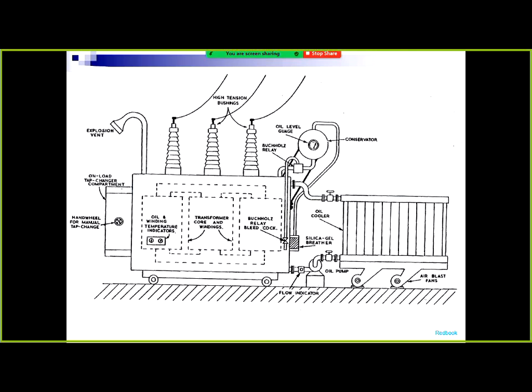So this is a typical looking transformer. It's a bit of an old picture. We don't have a hand wheel for the manual tap changer on the bottom left corner anymore. You've got the windings inside there. On the right hand side you've got your cooler, and that can be just natural convection, or it could be with pumps pumping it around, or pumps and fans. So there are those three types of cooling, and that depends on the temperature of the transformer. As you use pumps and fans, they use electricity, so your losses are higher. So if you're not heavily loaded, you don't turn them on at all, and your transformer doesn't get too hot.